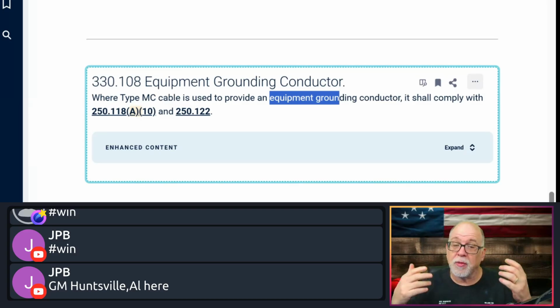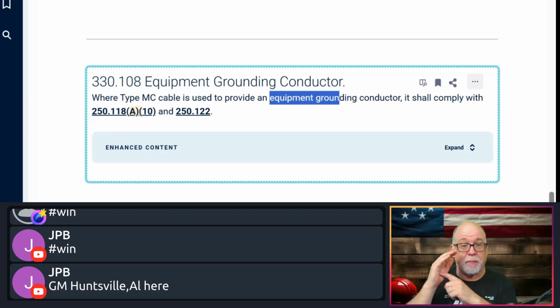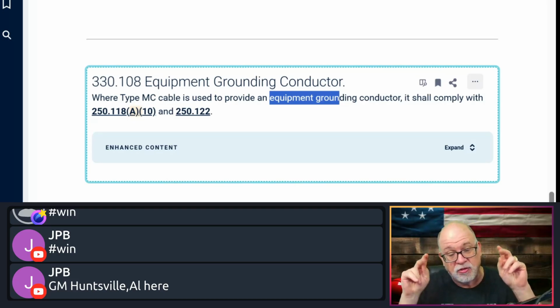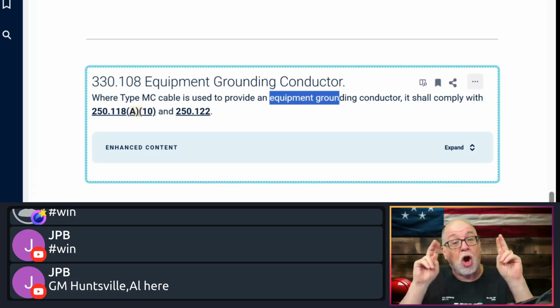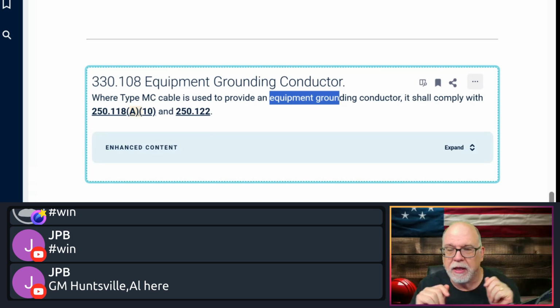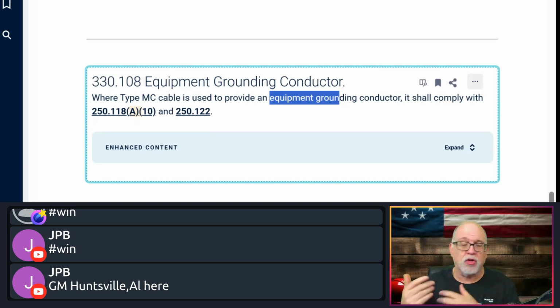That way, the armor can be used as long as you use a proper fitting. You can't use a standard fitting. It's got to be an MCI-A fitting. Think of the A as advanced, or think of the A as the armor being used as an equipment ground. Then at that point, you don't have an equipment ground in there. Okay, that type of thing.